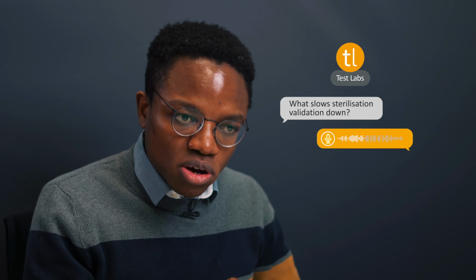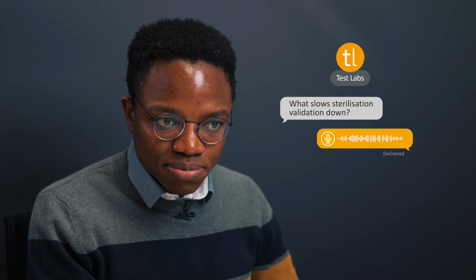Number two, what packaging are you recommending your device be packaged in during sterilization? Because different packagings have different levels of steam penetration, which will increase or decrease the sterilization efficacy you're going to get with your medical device. And another thing you might not know is that the actual packaging itself also has EN standards that it needs to meet to make sure that it's also doing its job properly within the autoclave. So it's always the things you never thought to look at that end up being the biggest issues. And once again, it's so important to have an expert on your side when you're navigating this process.